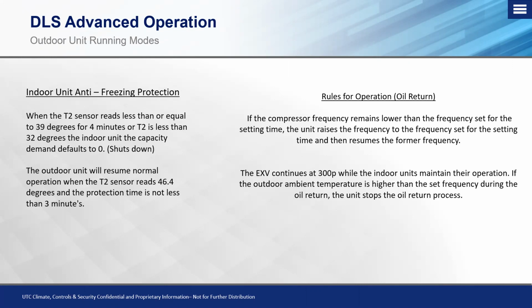And that usually is enough because we don't have a dedicated sensor just focused on oil lines. We're just using our outdoor temperature sensors and our indoor temperature sensors for coil temperature to dictate a low oil situation for a time where we've been running at part load and we need to start recirculating oil back because there could be a potential starving situation for the compressor. So the EXV will continue at 300 pulses while the indoor units maintain their operation.